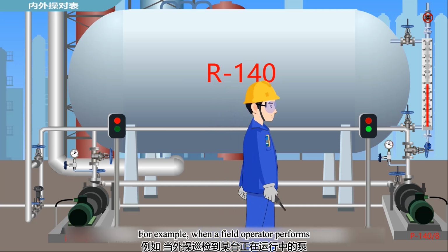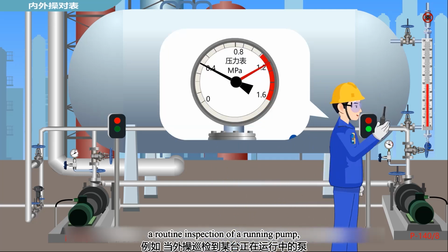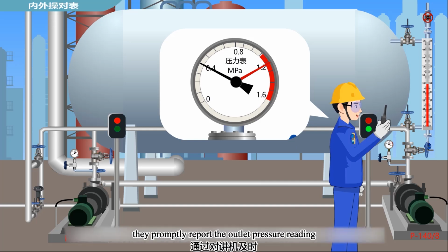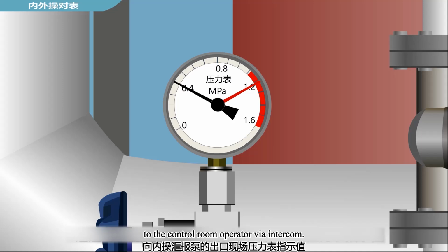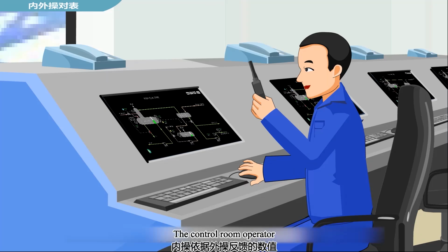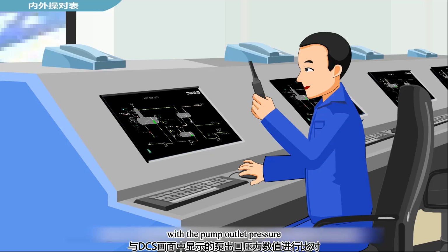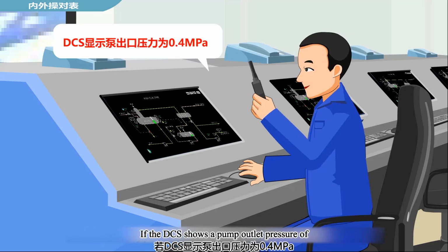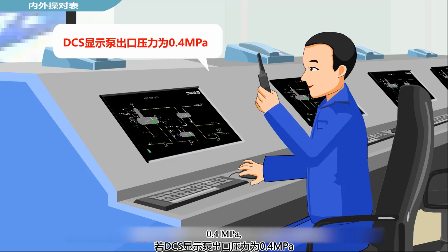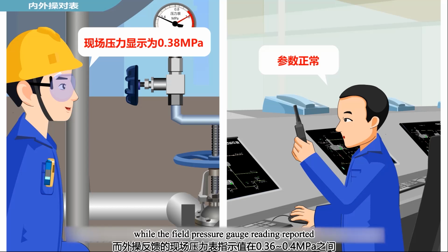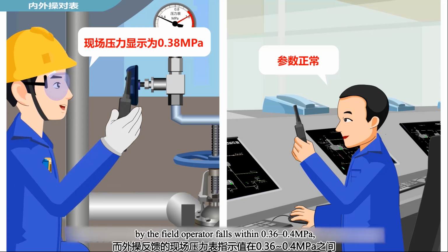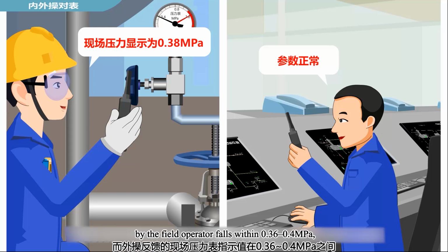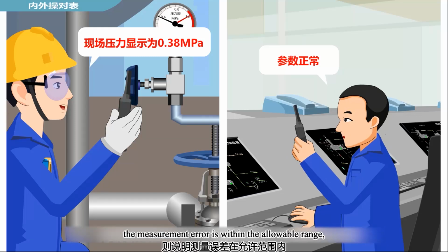For example, when a field operator performs a routine inspection of a running pump, they promptly report the outlet pressure reading from the field pressure gauge to the internal operator via intercom. The control room operator then compares the reported value with the pump outlet pressure displayed on the DCS screen. If the DCS shows a pump outlet pressure of 0.4 megapascals, while the field pressure gauge reading reported by the field operator falls within 0.36 to 0.4 megapascals, the measurement error is within the allowable range, indicating normal operating parameters.